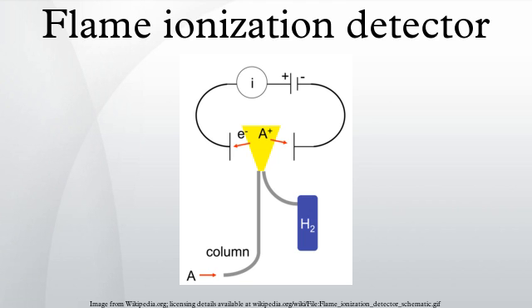The manner in which the final data is displayed is based on a computer and software. In general, a graph is displayed that has time on the x-axis and total ion on the y-axis. The current measured corresponds roughly to the proportion of reduced carbon atoms in the flame.